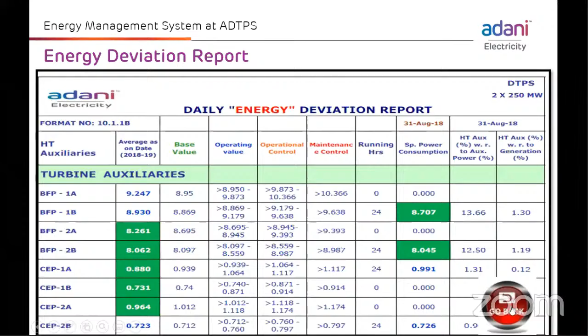Based on this monitoring, there are various MIS reports we are generating for the reviews, like the daily energy deviation report, monthly boiler energy deviation report, monthly turbine heater performance, and area-wise aux power, for identifying the areas where we are having some higher consumption. Air ingress in the boiler is also monitored, because the boiler is always operating at negative pressure, so there is always a chance through various peepholes or any ducts.